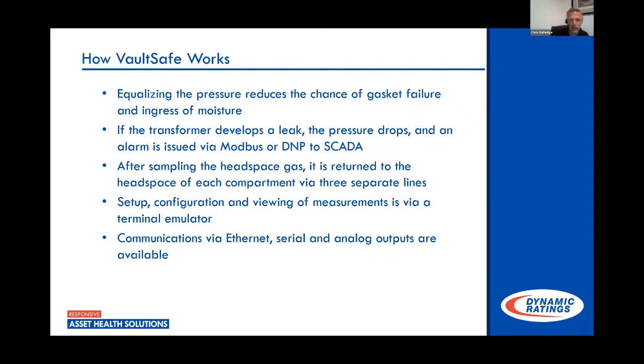You do have to do that locally when the monitor is installed, but you can set these values. You can also set it for a total PPM value. So if you want to go by IEEE guidelines and say, going from condition 1 to condition 2, I would like an alarm, and set that at 100 parts per million, you can do that. I would recommend at least getting some type of history for a transformer before setting a total PPM alarm, to eliminate false alarms, because again, 100, 150 is not that unusual for some transformers to see.